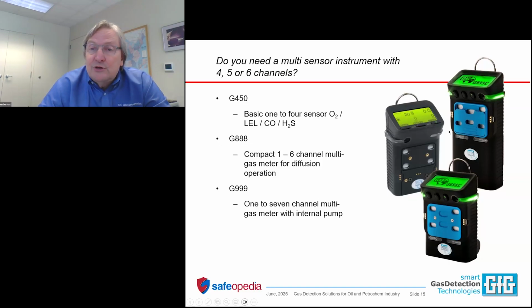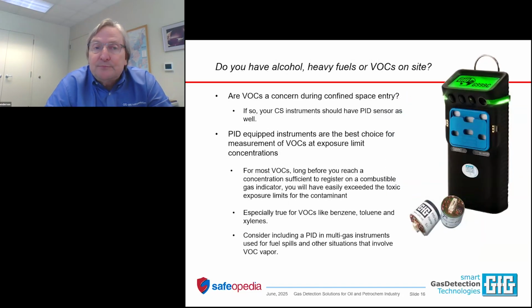And the third option would be a pump-equipped instrument. You can either have a basic diffusion instrument where you take the instrument into the area where the hazards exist, and the hazards simply diffuse into the sensors, or you can equip the instrument with a mechanical pump. When you turn the pump on, you're pulling the sample in through a hose and probe assembly. We'll talk more about that in a minute.